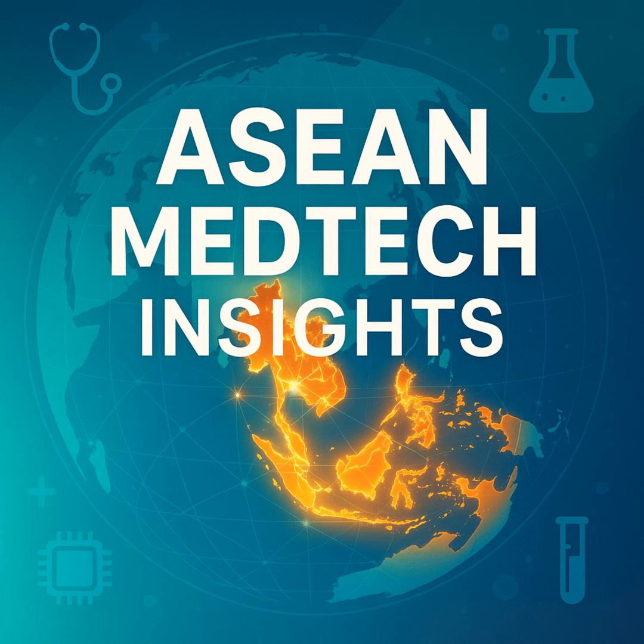Let's consider a real-world scenario. A company has a Class C diagnostic imaging software with CE marking under the EU MDR. To register in Singapore and Malaysia, they must prepare a submission based on the ASEAN CSDT. Their existing CER is a strong foundation. However, they must perform a gap analysis to ensure it meets local expectations.